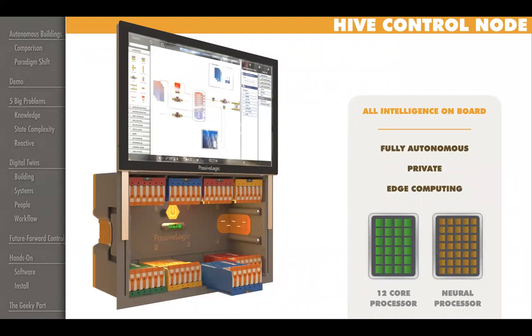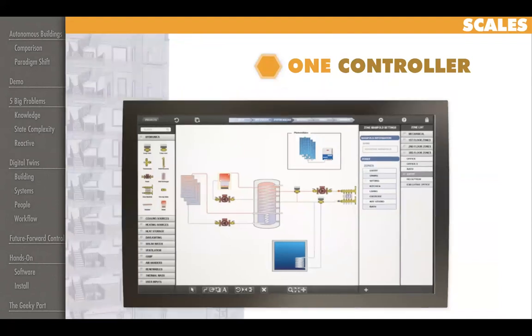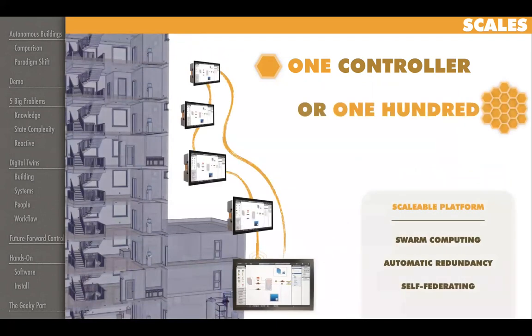Even if we could, it's not resilient enough to run things from the cloud. That's an important thing for everybody to understand. Why autonomous systems? By nature, they can't be driven from the cloud resiliently enough, even in the best of circumstances, even if you're at Microsoft's headquarters. And then you make that a scalable model — whether you have one controller or three, five, ten, a hundred, or five hundred. That's how PassiveLogic works: they're all software-defined boxes. There's no single Jace or master — they all can master. They all carry a copy of the database and work together to solve the overall building problem.